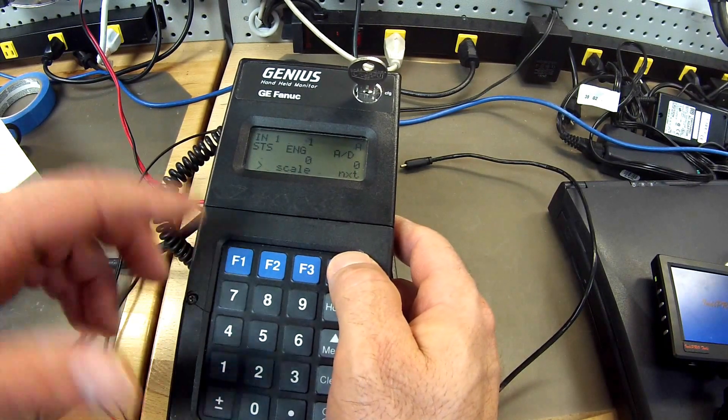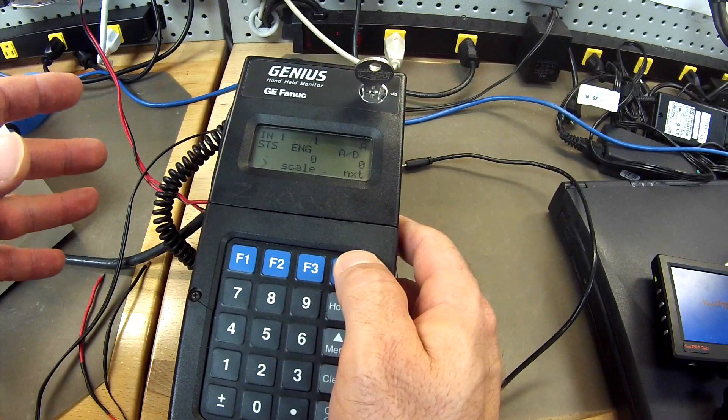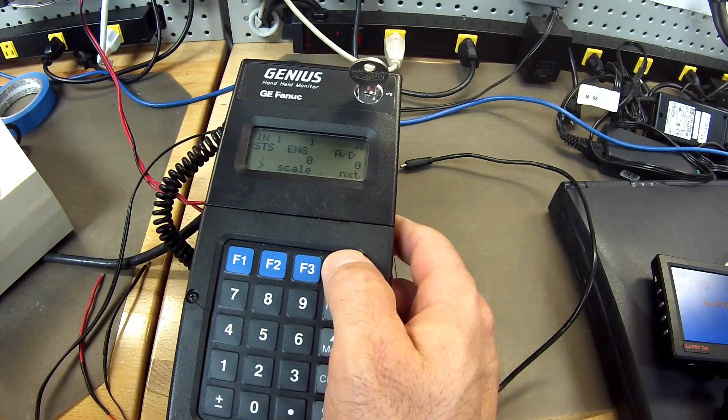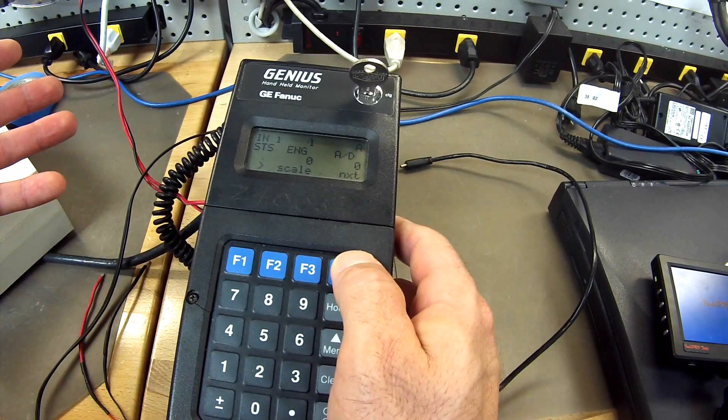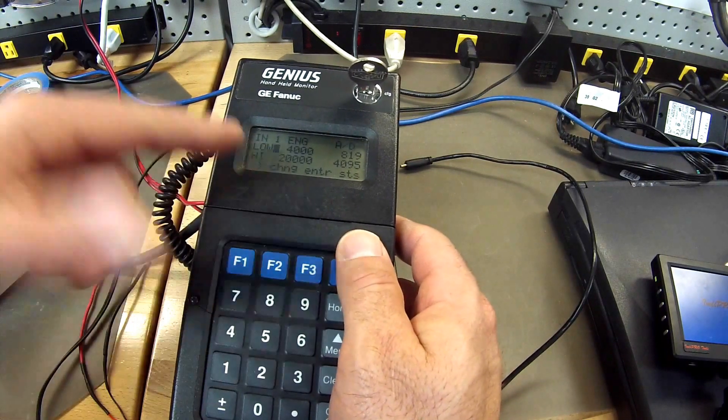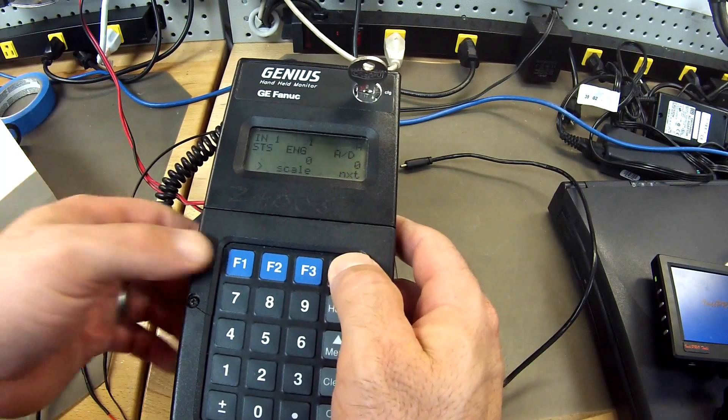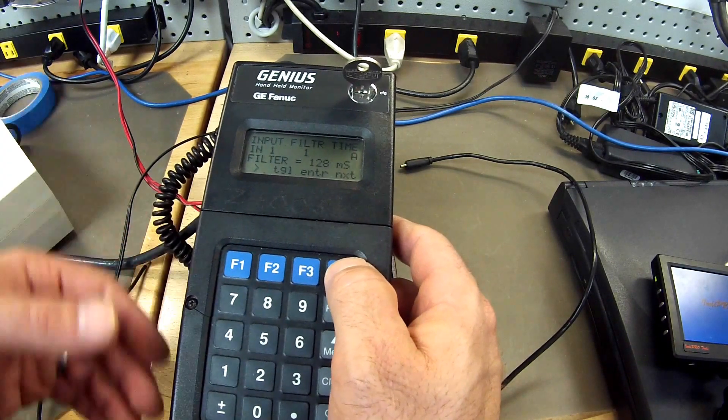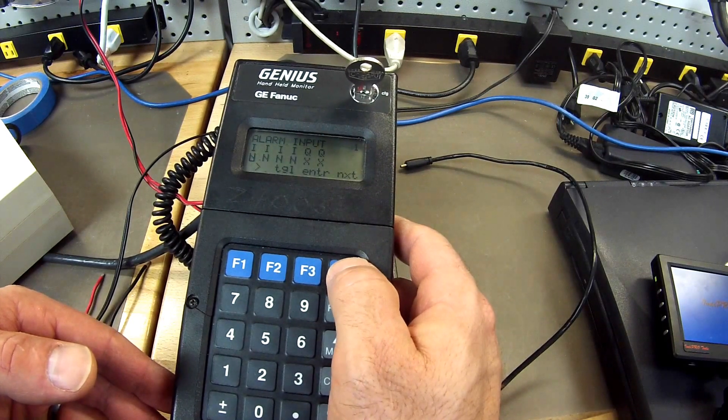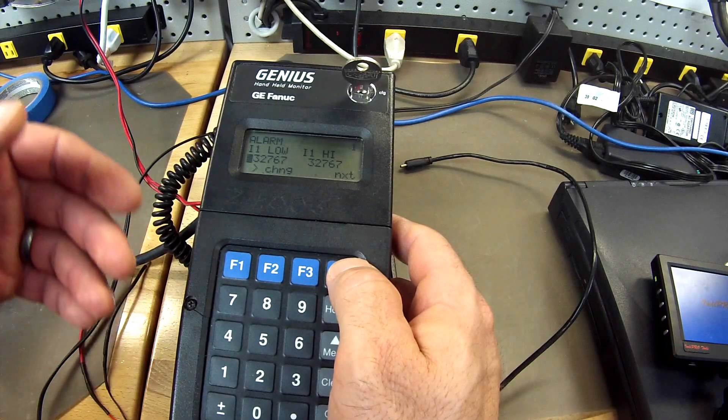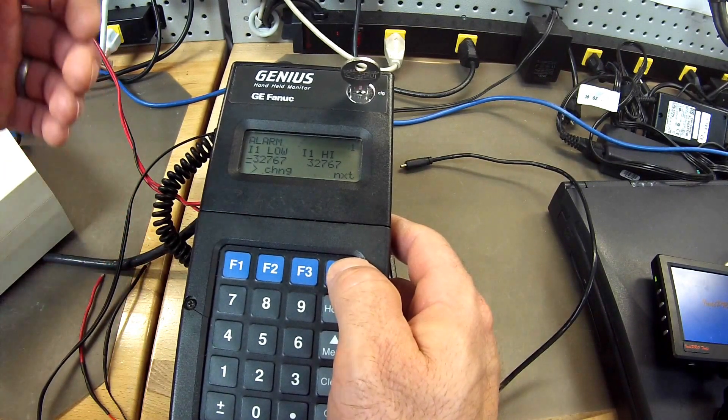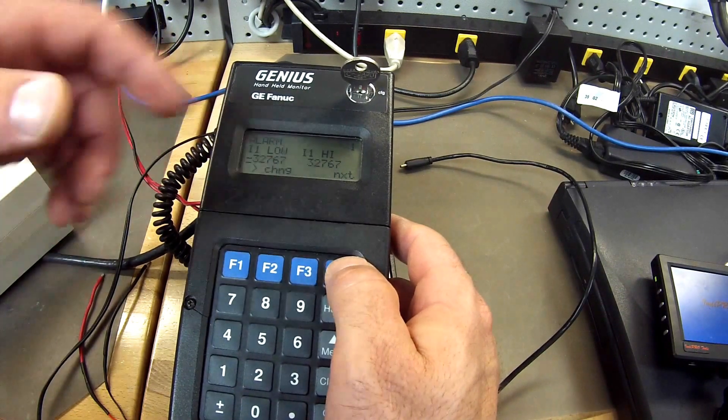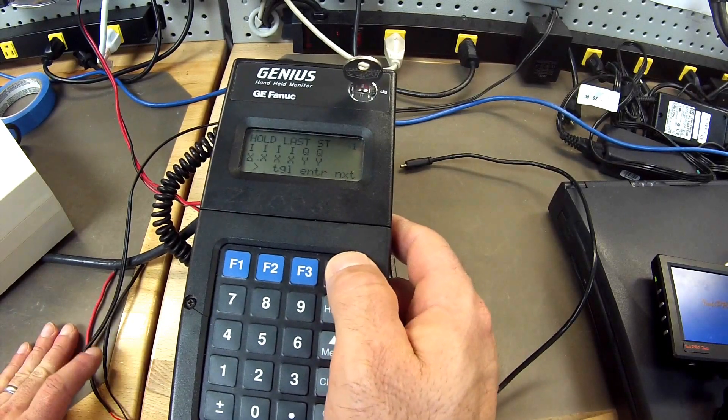So we hit next. My scaling is preset. If you are checking to see if your block is working, I would recommend that you leave your scaling the way it is, the way that it has been working in your plant or your factory or whatever application you are using it for. Mine is automatically set to the factory standards. And then next, filter, 128 milliseconds. Alarm input. My high and low alarm factory standard is negative 32,767 to a high of 32,767. That is the alarm range. That is factory standard. If you have something different that is fine.